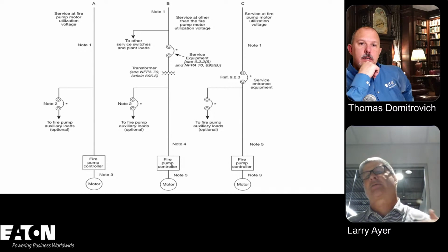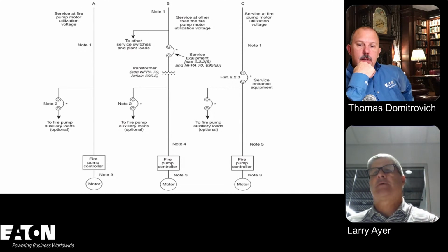I put this in there so people could look at each one. Look at the first one. That's a direct service connection. There is no overcurrent device or disconnect between there and the fire pump controller. The fire pump controller would be considered the disconnect. So that looks like it satisfies the requirement in A.